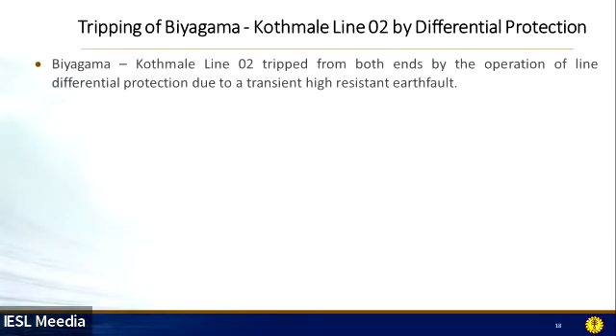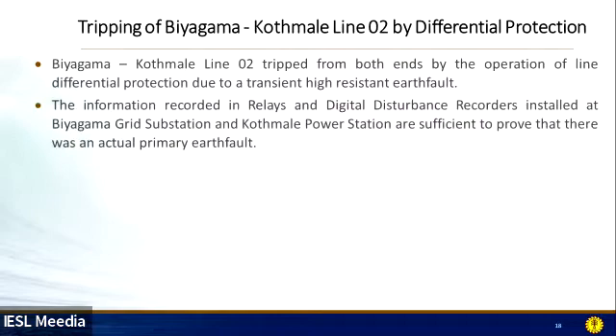So here, in this slide, I will be explaining the tripping of Biyagama-Kothmale line 2 by differential protection relays. First, the Biyagama-Kothmale line 2 tripped from both ends by the operation of line differential protection due to a transient high resistance earth fault. The information recorded in relays and digital disturbance recorders installed at Biyagama grid substation and Kothmale power station is sufficient to prove that there was an actual primary earth fault. That's our observation when we analyzed the events and records collected from relays and digital disturbance records.